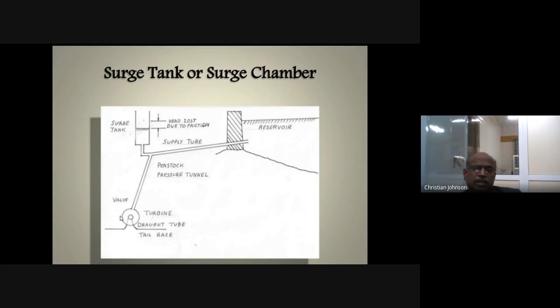As I was saying, one of the advantages, the attractive feature of the hydropower station, is its instantaneous start and instantaneous stop. When it is instantaneously stopped, the water which was flowing below into the powerhouse is now stopped in the vicinity, but from here the water is still flowing and it will be hitting the water which is already stopped. So there is a possibility of hammering action. Water hammer pressure will be building, and the entire shaft will be building with higher pressure.